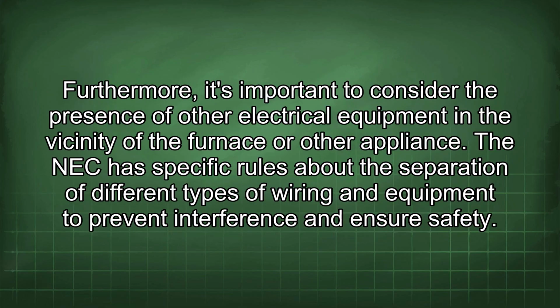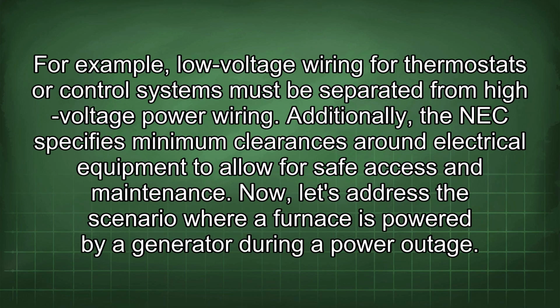Furthermore, it's important to consider the presence of other electrical equipment in the vicinity of the furnace or other appliance. The NEC has specific rules about the separation of different types of wiring and equipment to prevent interference and ensure safety. For example, low-voltage wiring for thermostats or control systems must be separated from high-voltage power wiring. Additionally, the NEC specifies minimum clearances around electrical equipment to allow for safe access and maintenance.